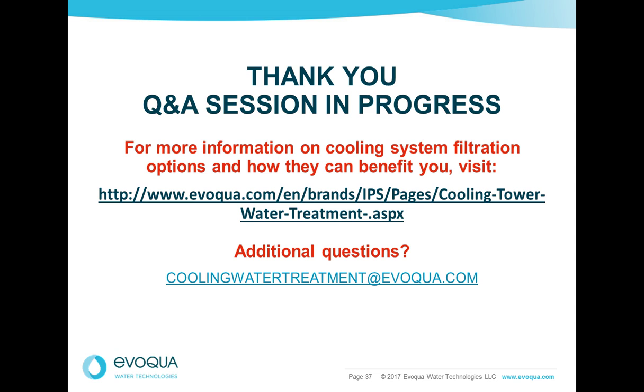It's funny, a quick example. I was at a site, a food processing plant, a few years ago. They were looking at installing a sidestream filter, and as I'm walking up to it, I couldn't even see the tower, and I'm smelling bleach. It was overwhelming. I walked up to it and it looked turbid, and it smelled like a hot tub, quite frankly. The operator's like, well, we don't have any microbial problems. I said, well, yeah, I can see that. Nothing's going to grow here. But I said, what are your corrosion rates? He said, well, we're having a lot of leaks throughout the system. That's why they're thinking about installing a filter. And I said, well, you're solving one problem but creating another.